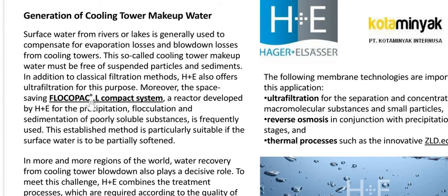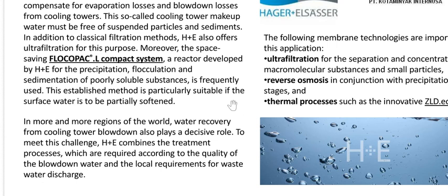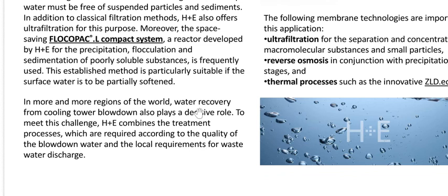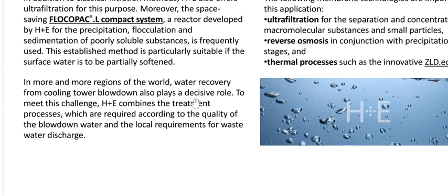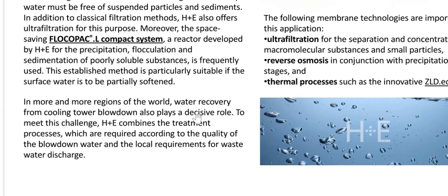Moreover, the space-saving FLOCOPAC L compact system, a reactor developed by H+E for the precipitation, flocculation, and sedimentation of poorly soluble substances, is frequently used. This established method is particularly suitable if the surface water is to be partially softened. In more and more regions of the world, water recovery from cooling tower blowdown also plays a decisive role. To meet this challenge, H+E combines the treatment processes which are required according to the quality of the blowdown water and the local requirements for wastewater discharge.